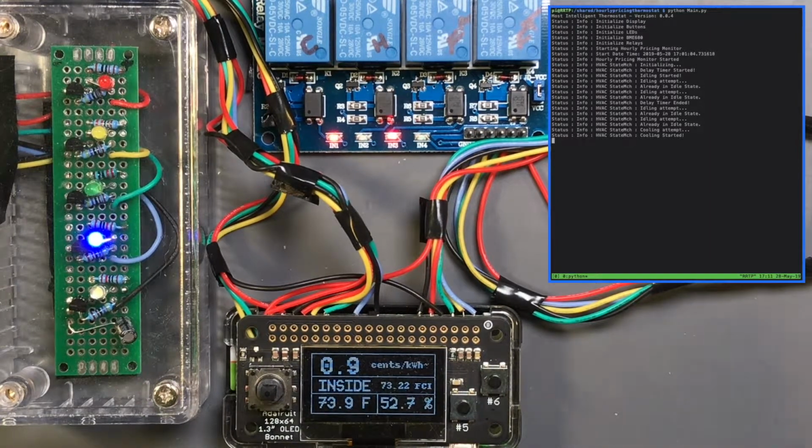In the state machine, everything always comes on sequentially, never in parallel. There's always an inserted delay between one relay coming on and the next relay coming on. That is to minimize the inrush current, so that if we're running this off of battery, or whatever we're running it off of, we minimize inrush current on anything that is being powered. The air conditioning has come on.